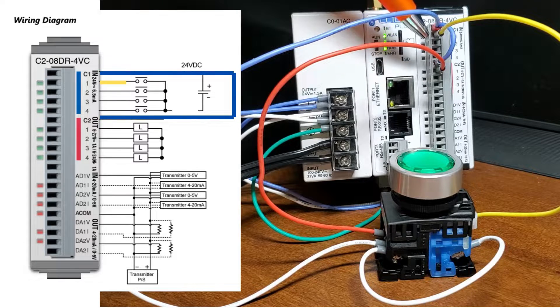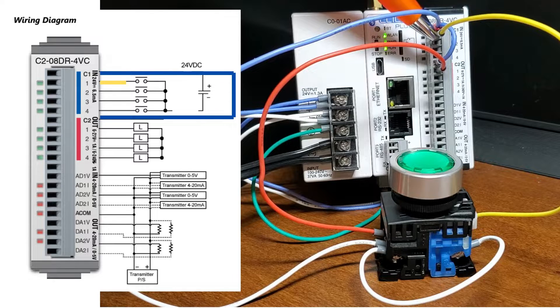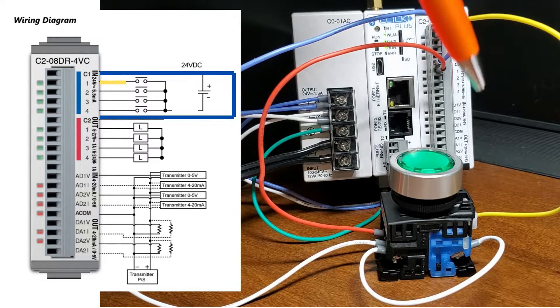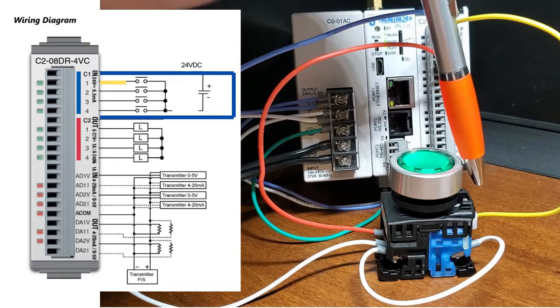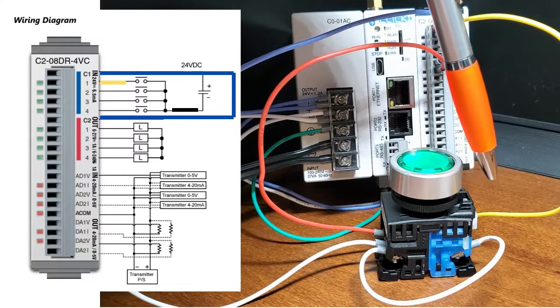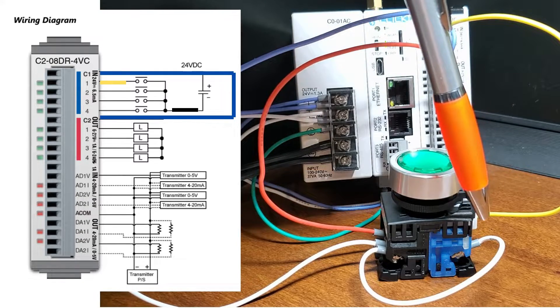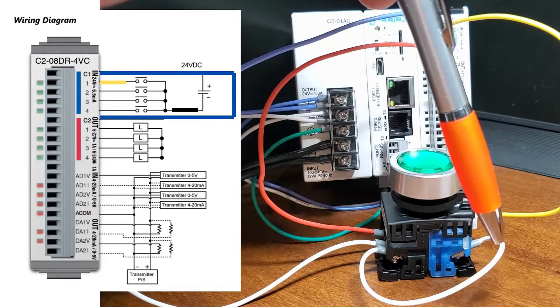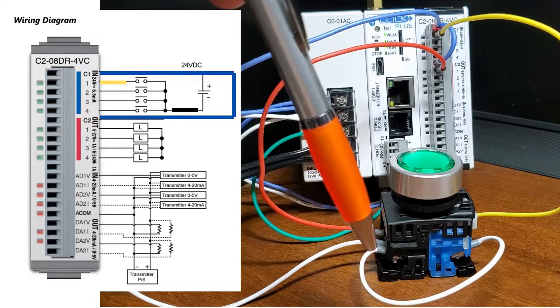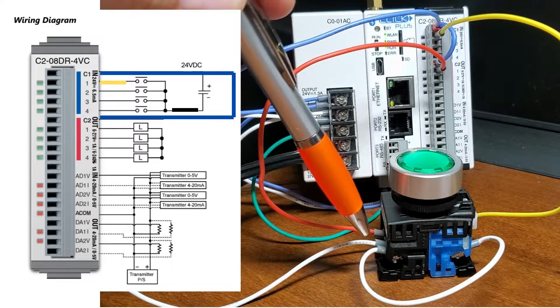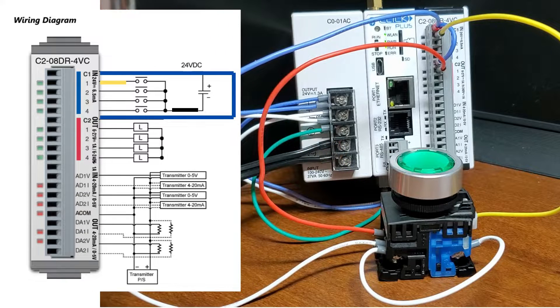The first input is wired to one side of the normally open contact of the pushbutton switch. The other side of the contact is wired to the 0V DC supply completing the circuit. Pushing the button will provide voltage to the input of the PLC.